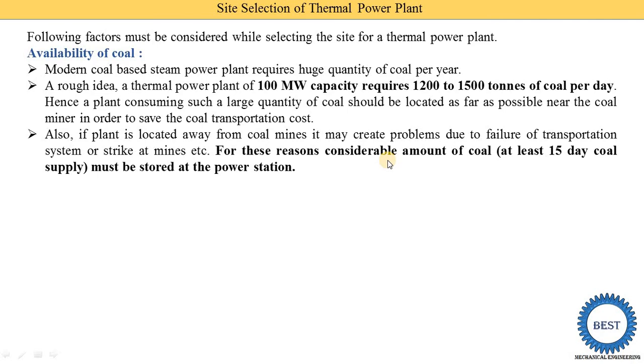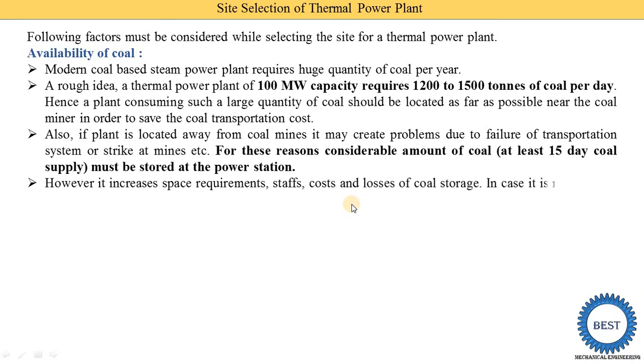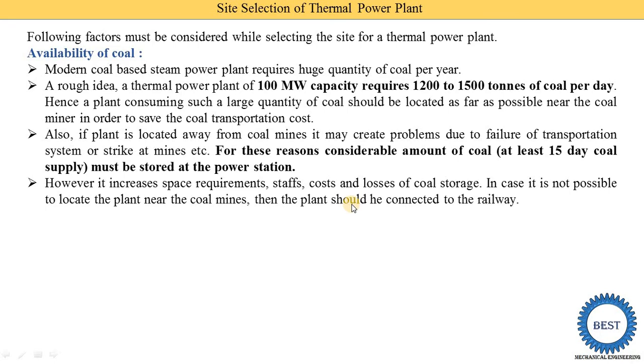We need to store 15 days' worth of coal as storage. For example, if one day requires 1500 tons, then we need to store 1500 tons multiplied by 15 days. However, this increases the space requirement, staff cost, and losses of coal storage. In case it is not possible to locate the plant near the coal mines, then the plant shall be connected to the railway. We need to select sites which are near to coal mines or connected with the railway.